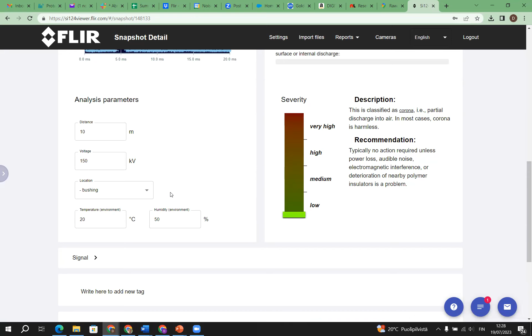This is the pattern of the partial discharge, the acoustic pattern. We included here the location, which was a bushing, and the voltage of the specific installation, which is very important. And then it gives you the severity assessment. In this case, the severity of this partial discharge is very low. The description is, as you see here, classified as corona. In most cases corona is harmless, and typically no action is required, unless there's a power loss or audible noise, which is actually audible here. But I think the audible noise is more a problem for neighbors or people working around, and the deterioration of the nearby polymer insulators. Of course, if the insulators are visibly deteriorated, then you need to take action. This is one example of a harmless partial discharge.